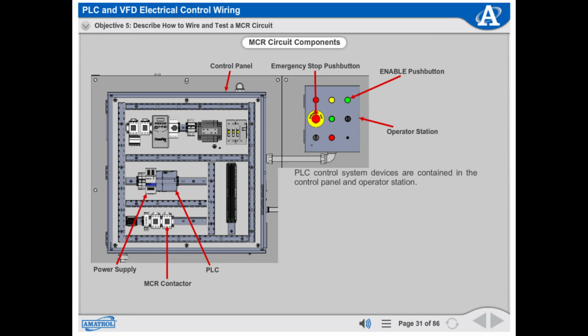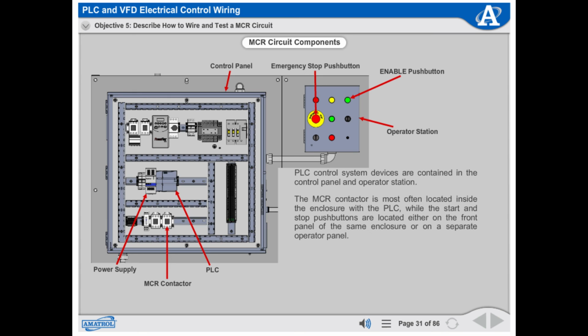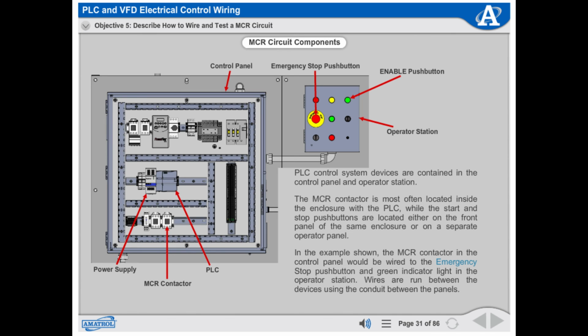PLC control system devices are contained in the control panel and operator station. The master control relay contactor is most often located inside the enclosure with the PLC, while the start and stop push buttons are located either on the front panel of the same enclosure or on a separate operator panel. In the example shown, the master control relay contactor on the control panel would be wired to the emergency stop push button and green indicator light in the operator station. Wires are run between the devices using the conduit between the panels.